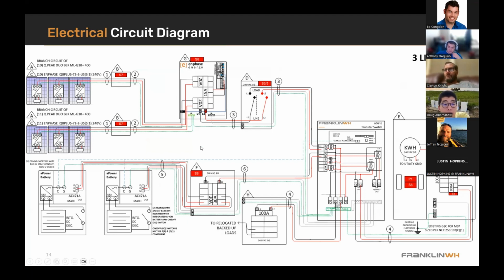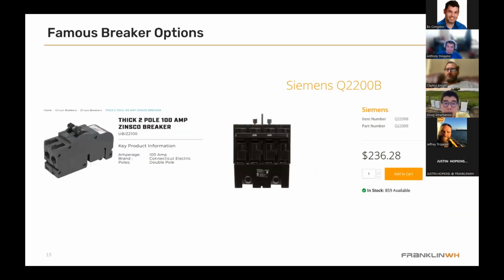So the other balance of system you need is this combiner panel. Then you basically have the full functionality of a 200 amp service on a 100 amp service, avoiding the main panel upgrade costs and dealing with the utilities, especially if you're located within 3 feet of the gas service - that's going to kind of freeze up everything if you're in California.